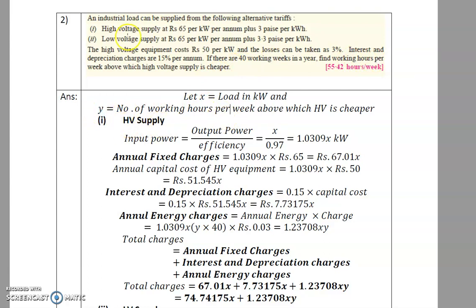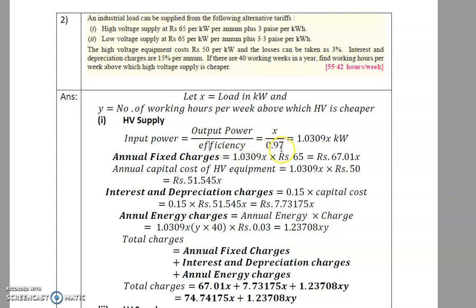For HV supply, input power = output power / efficiency. Since losses are 3%, efficiency is 0.97, so input power = x / 0.97 = 1.0309x kW. Annual fixed charges = 1.0309x × rupees 65 = rupees 67.01x. Annual capital cost of HV equipment = 1.0309x × rupees 50 = rupees 51.54x.